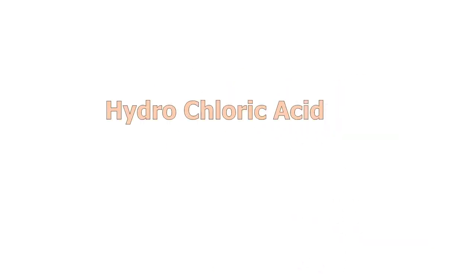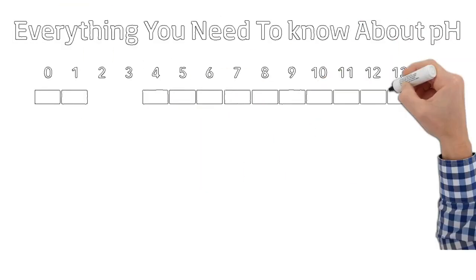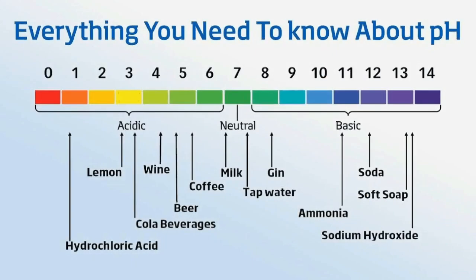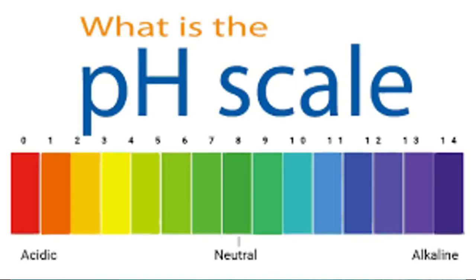Hydrochloric acid is used to reduce the pH of the raw water. The quantity of hydrochloric acid depends upon its concentration, the flow rate of water, and the recommended pH of water for RO membranes by the manufacturers. However, less than 7 pH water is fed to the RO membranes.